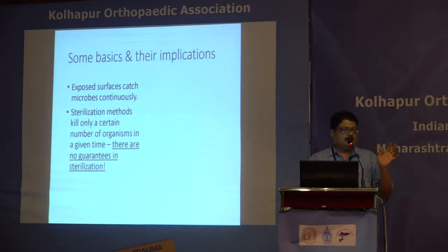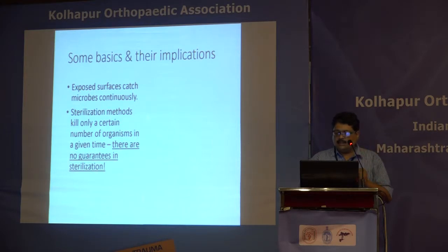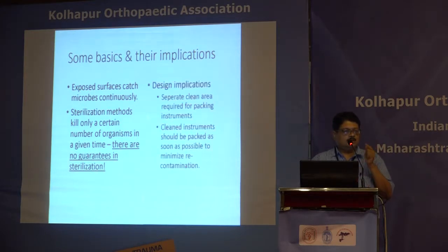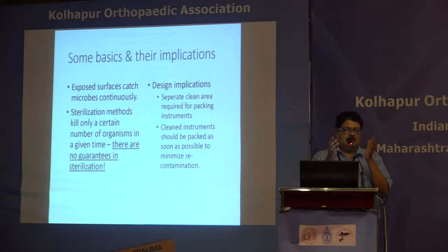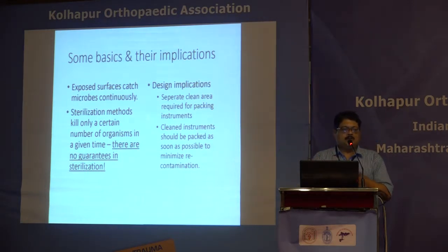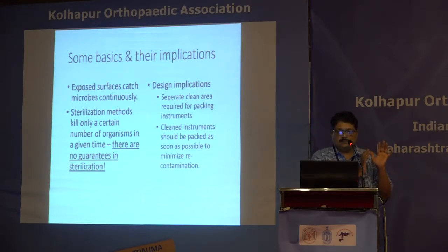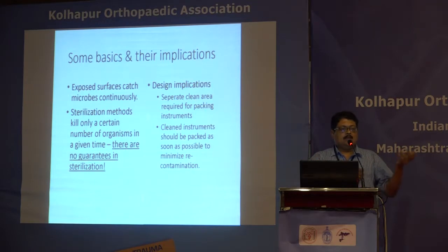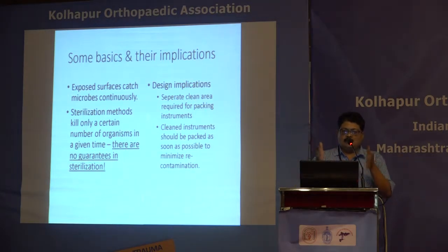This has implications on CSSD design. Once we wash an instrument, we have to make sure it does not get recontaminated again, because the sterilization process is going to kill only a fixed number of microbes. If you start out with more, then something may remain back. Therefore the area where you pack drums and trays has to be very clean to prevent recontamination.